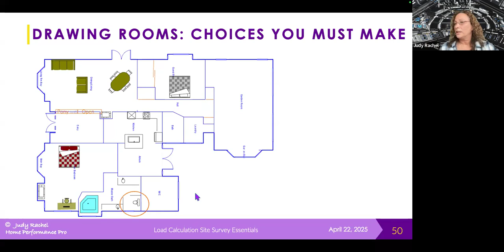So small closets are usually combined with the adjoining room. Large closets, entryways, and hallways, if they're 100 square feet to 150 square feet, then the procedures tell us that those should be treated as separate rooms. Just because we treat something as a separate room doesn't mean that we have to condition it directly. It just gives us the chance to look at those loads and figure out whether they can be conditioned by proximity to adjoining rooms, or whether there is enough load in them that we really do need to put direct conditioning into them.